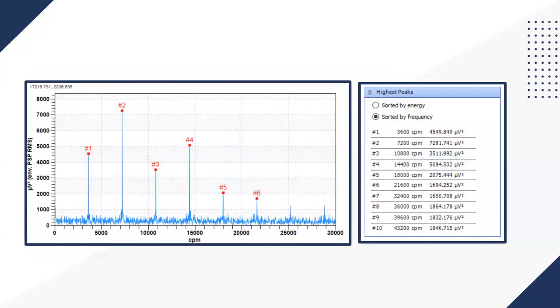Again, we can see in the FFT or the spectrum, 60 hertz, 3600 CPM. Here is my evidence of repetitive impacting, or repetitive signal. My 2 times is my dominant peak, which is showing me that I have a corona effect going on.